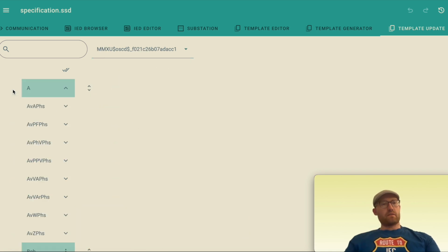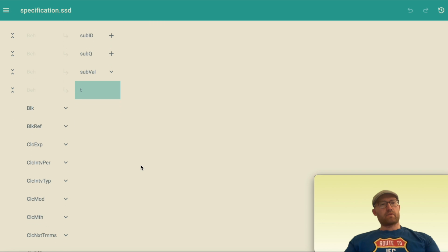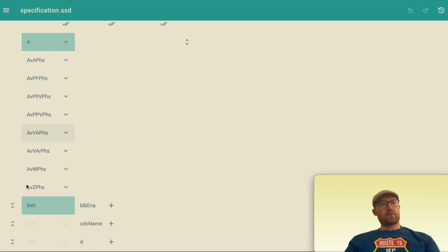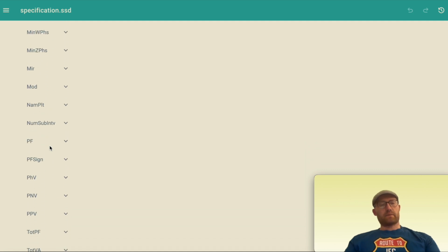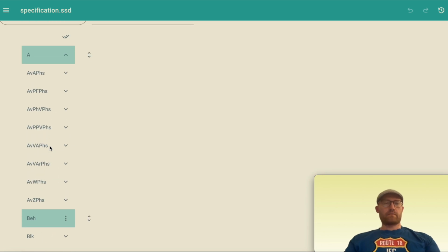So what you can see here is the selection, all the green highlighted things. This is the information that you find in an SCL file. But in addition to that, there are other data objects that you can see. And these data objects are parsed by this plugin through a file called NSD, namespace description. This is basically the tables that you can find in the IEC 61850 7-4 and 7-3, partly 7-2 and 8-1, all in machine readable format, an XML file.